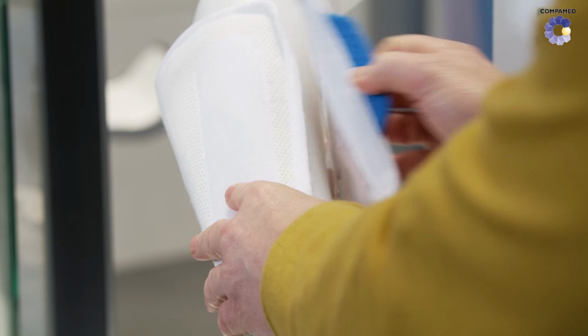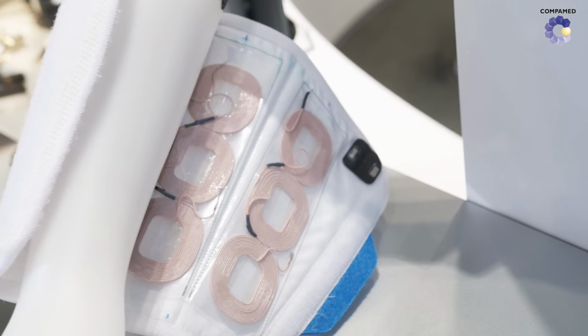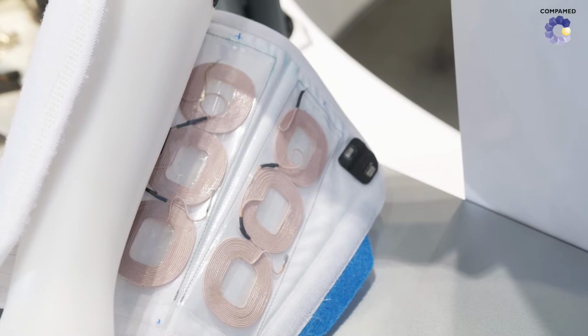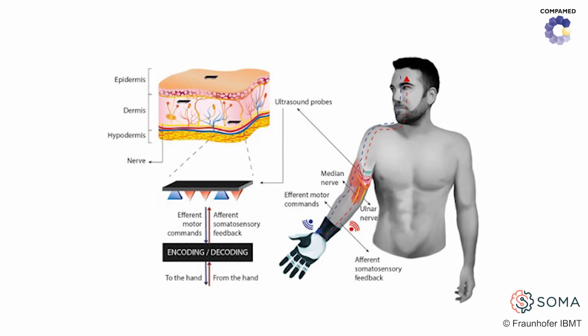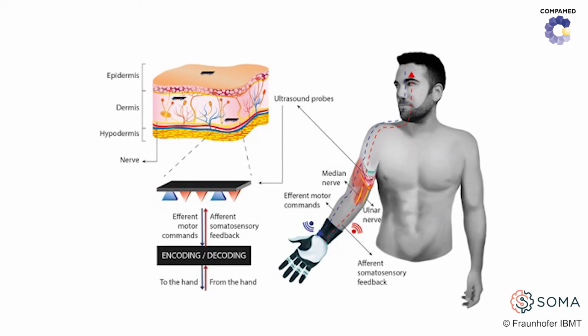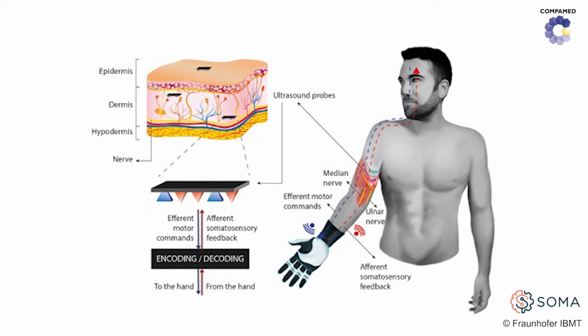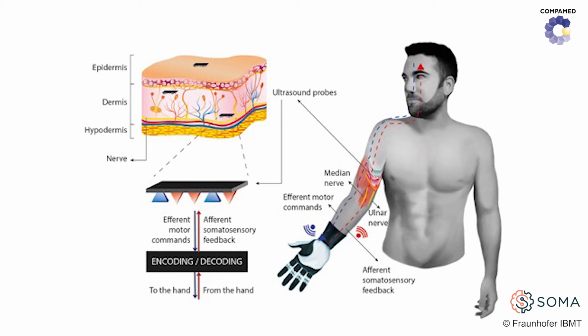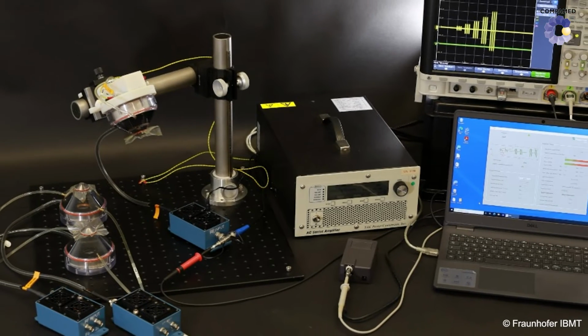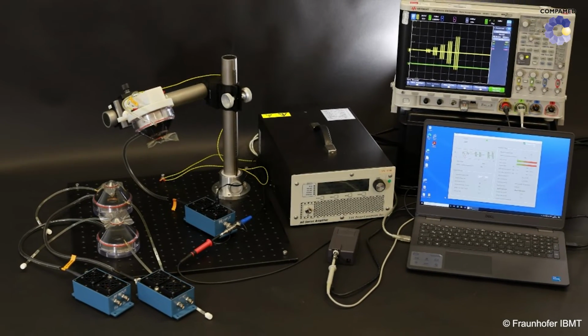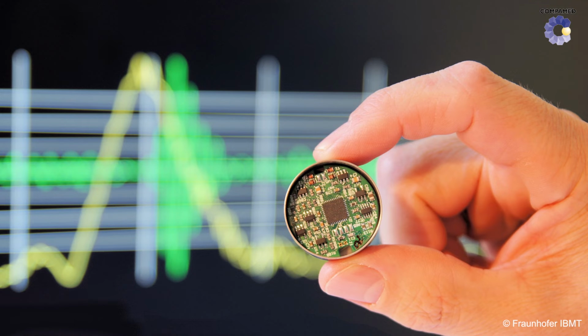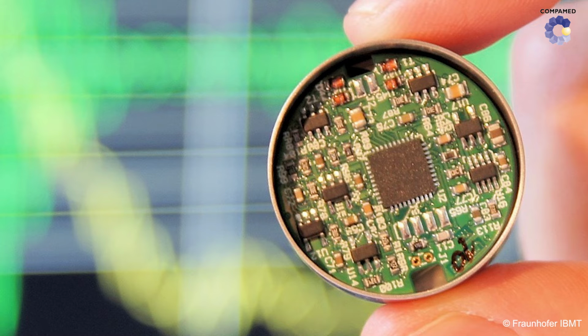An established method at this point is inductive coupling. The technical limitations here are due to the fact that a near field is very strongly dampened by the body, and then I have to position corresponding coil pairs very closely to each other. However, the Fraunhofer IBMT also has experience with energy injection via ultrasound. The advantage of ultrasound is that due to the good coupling of the transducer to the body, I can also supply very deep-set implants with energy. I can also penetrate titanium housings with ultrasound.